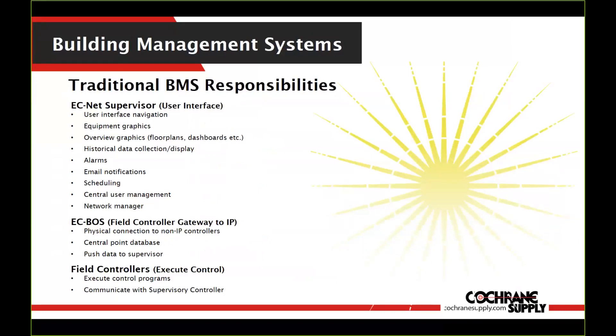The responsibilities are divided amongst those pieces of equipment. The supervisor does your user interface, navigation, graphics, overview graphics, historical data collection and display, alarms, emailing, scheduling, and all user management. It manages the network devices, those EC-BOSes, and has the central database and data model of your system. The EC-BOSes below are the gateway to your server — they have a replica of the point database for whatever field controller system they're monitoring, and they push the data up to the supervisor. Field controllers just execute the control of the system, not doing any UI or network management.